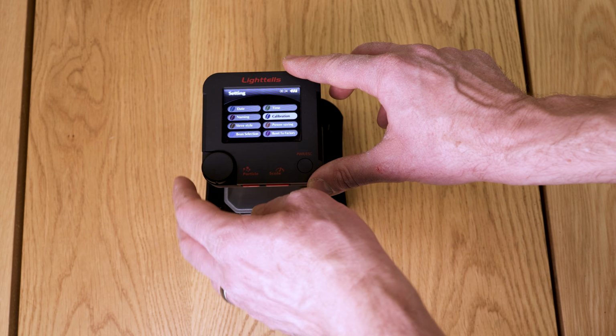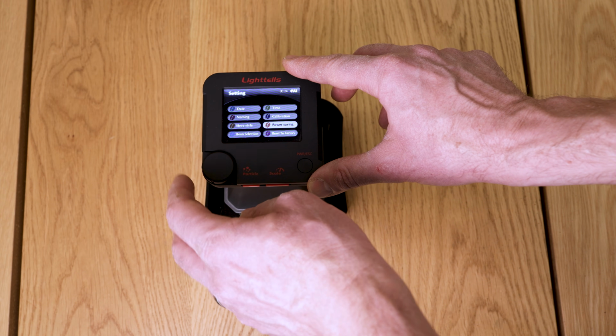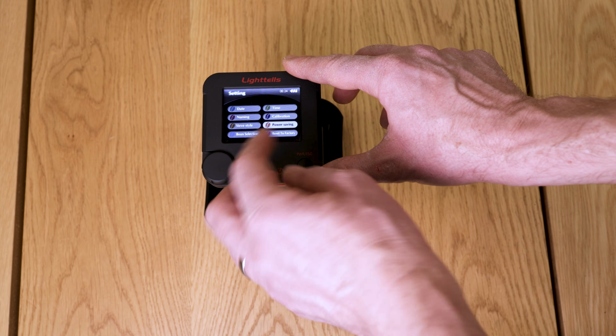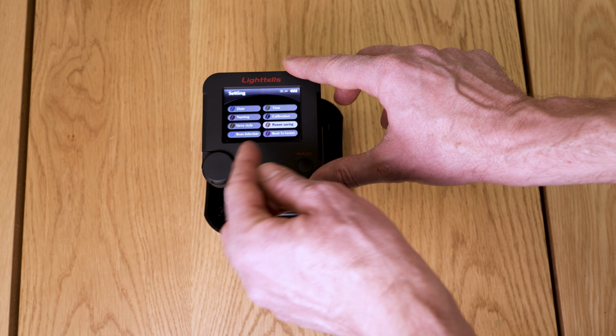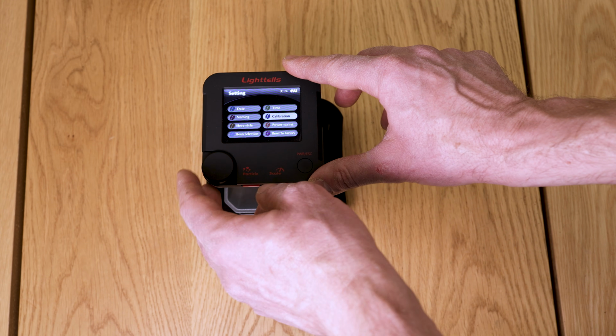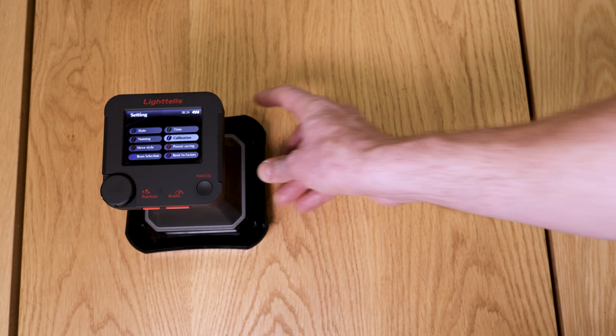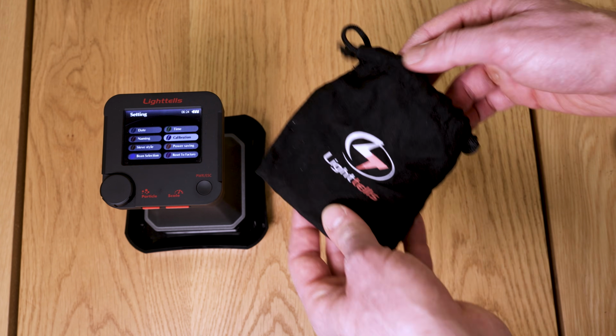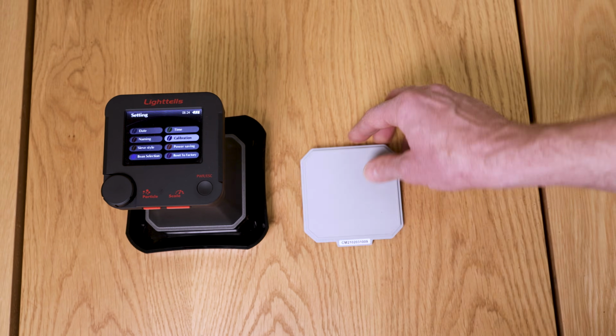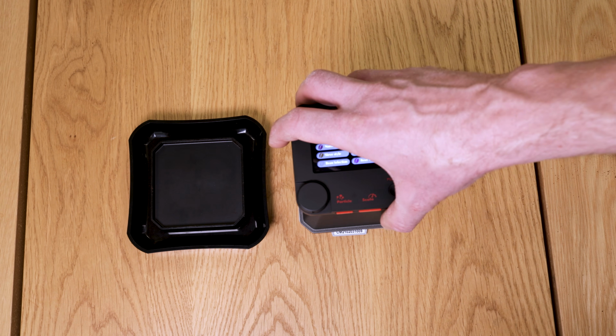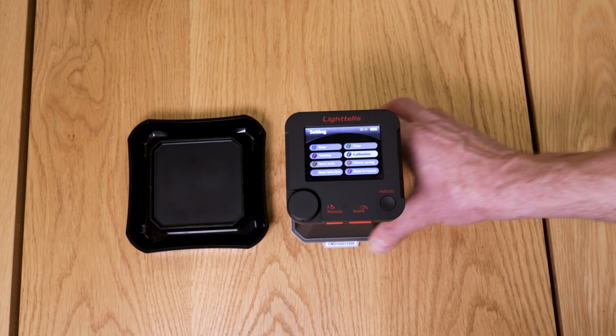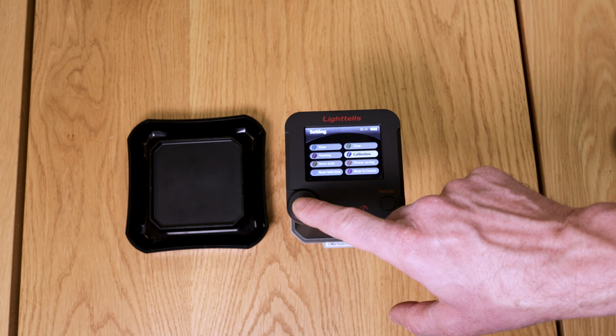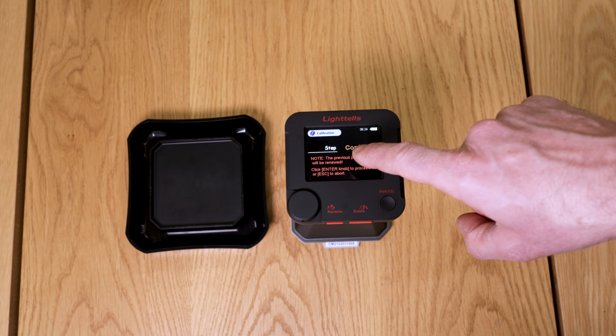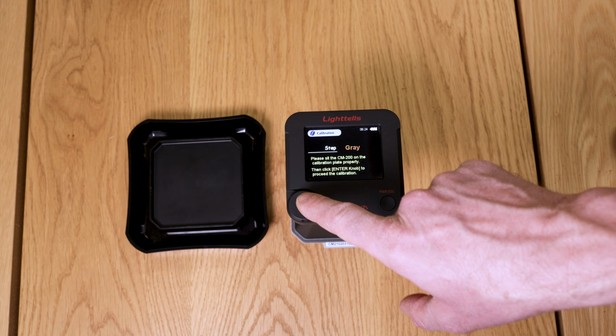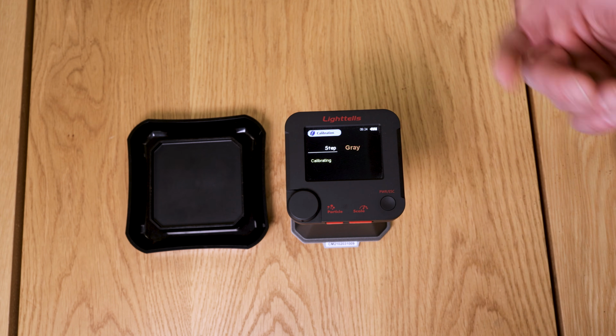it out. Calibration, we are going to do a calibration right now. Power saving is then again when the device is going to be switched off and reset to factory. So yeah, do the calibration. Again, here the little calibration plate is packed in this little bag so that it's protected from the sun and it's not going to change its color. Then I go to calibration. I have to confirm twice. Now it's calibrating.